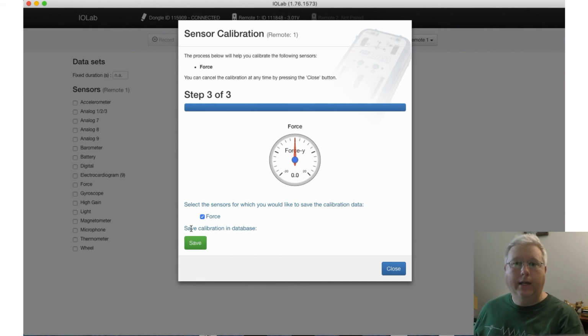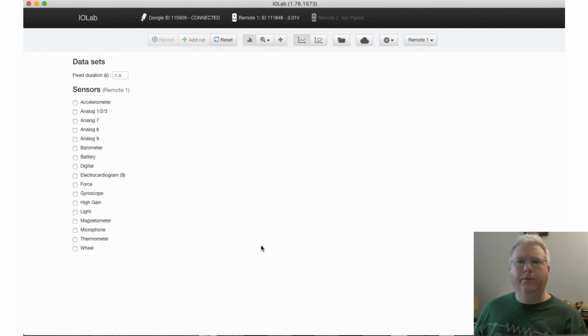All right, well, it's not quite calibrated yet, you still have to save it. So you have to make sure that you press this green save button here. Sometimes as I've been going through and calibrating, I've accidentally hit close down here, and if you do that, then it won't save the calibration. So make sure you click save when you do this. And if for some reason during the semester you have to use a different laptop to complete the lab, you have to recalibrate the sensor, because the calibration actually calibrates the sensors of the device to the computer. So if you change computers mid semester, make sure you recalibrate to the new computer.